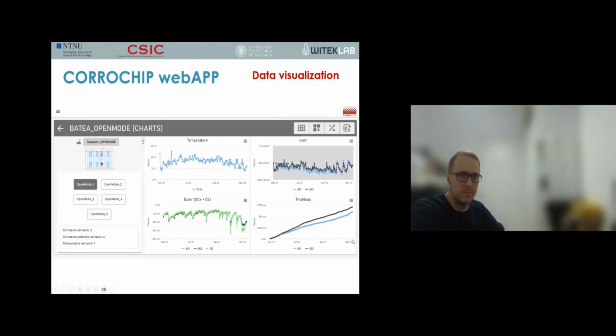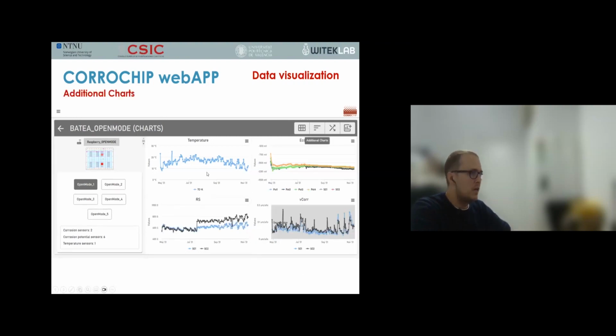In the additional chart, we can see again the temperature, the potential. We have the capability of providing the corrosion potential of four extra electrodes in case of need, if the user wants to install them. We also provide the electrical resistance of the sensors, of the cover between the sensor and the outer layer, and also the estimation of the corrosion rate.